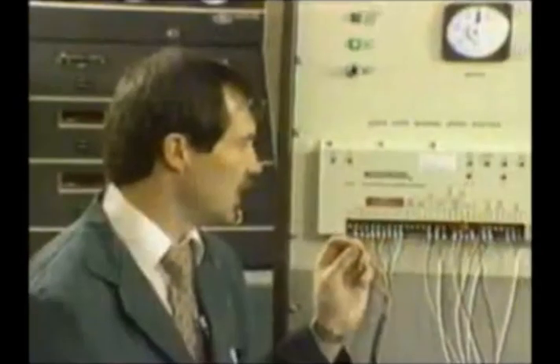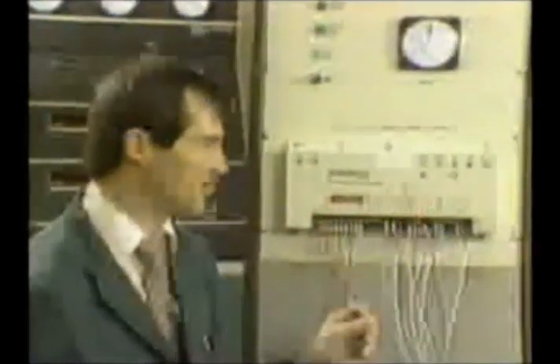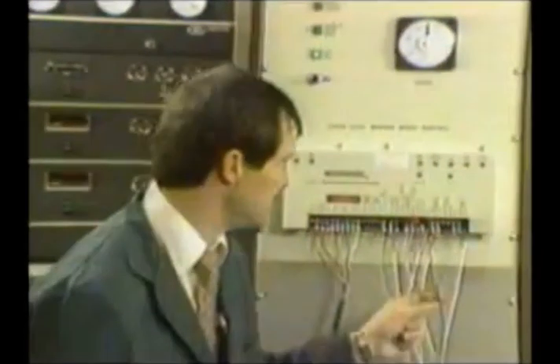One thing I haven't mentioned yet is our start fuel limiter potentiometer. With this added feature, we can set up so instead of calling for maximum fuel on startups, you can limit that amount of fuel you're calling for to get smoother, quicker startups. Also, it will allow you for less emissions from your prime mover control. To set up your start fuel limit, you need to measure your unloaded actuator voltage or no load actuator voltage.